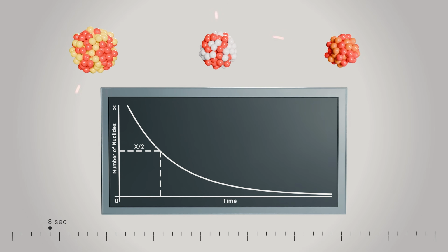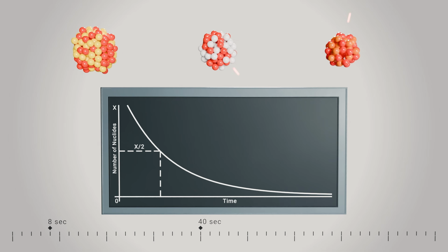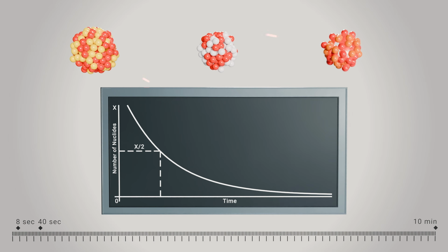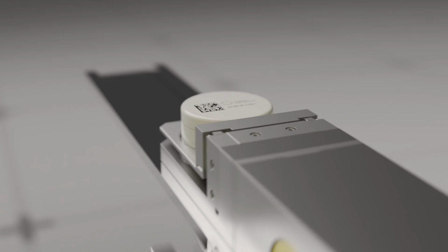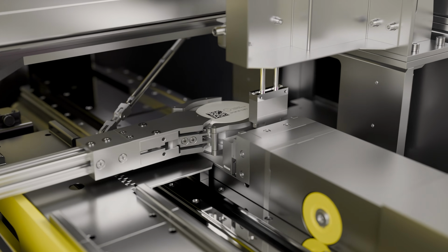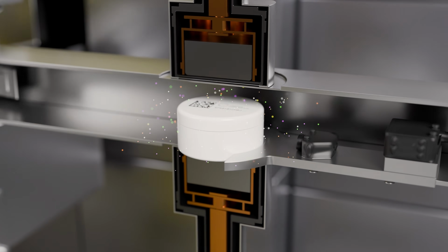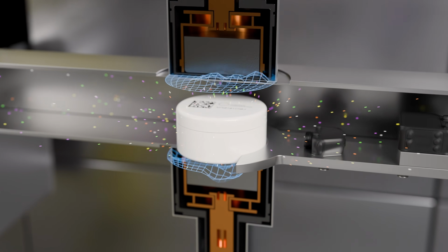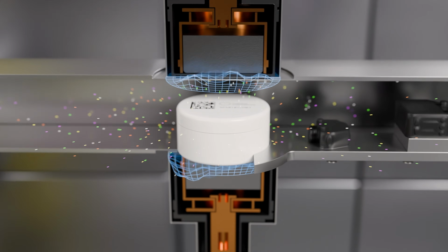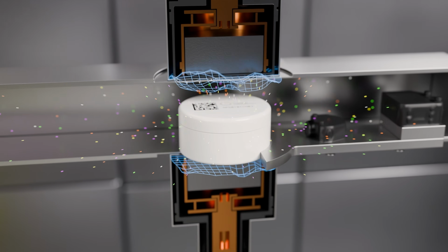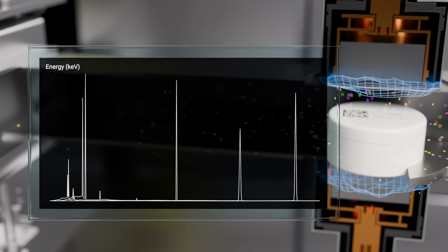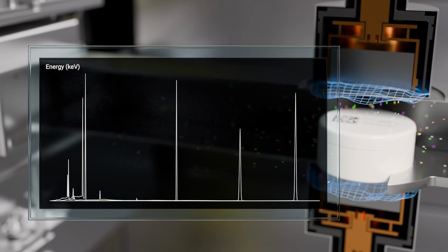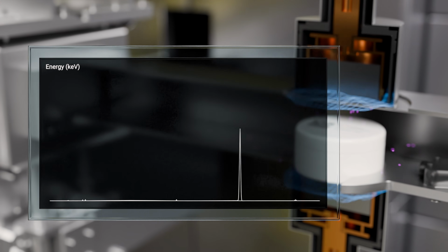The half-lives of the activated nuclei are very short, ranging from seconds to a few minutes. This means their activity can be measured quickly and decreases very rapidly after analysis. Once activated, the sample is moved quickly to the detection stage. Here, ultra-sensitive, supercooled germanium detectors precisely measure the gamma rays emitted from both the sample and the reference disk. These detectors are the gold standard for high-resolution spectroscopy, allowing PhotonAssay to easily distinguish between the signatures of gold, silver, copper, and the reference disk elements.